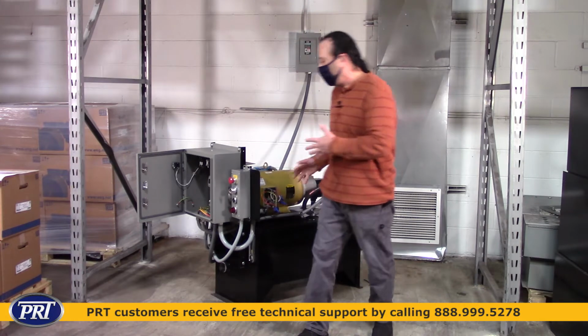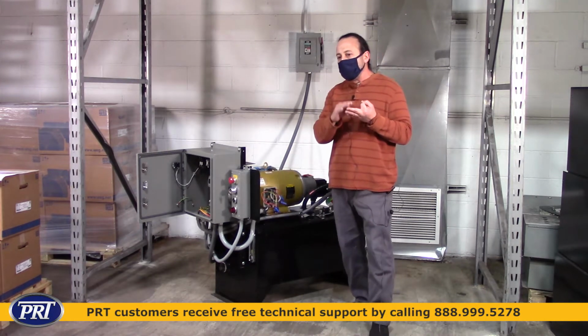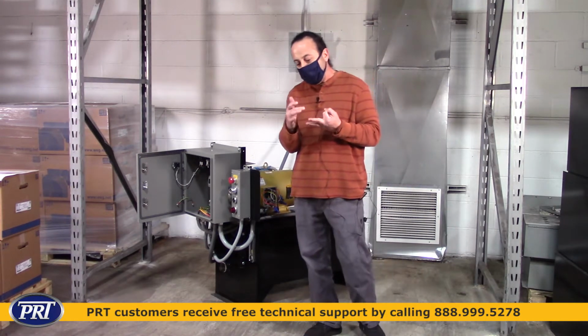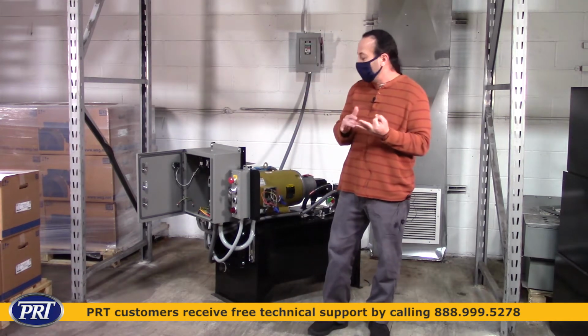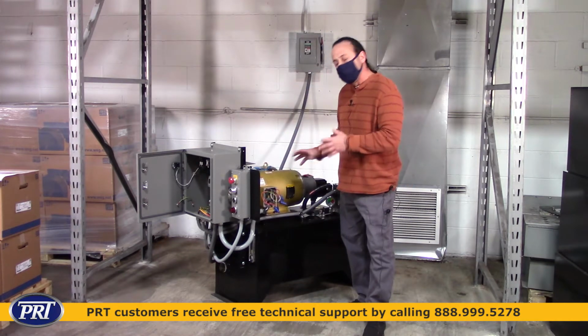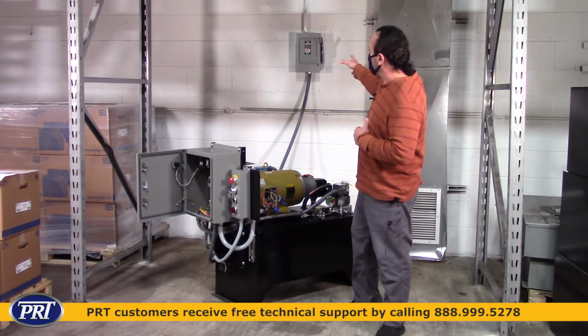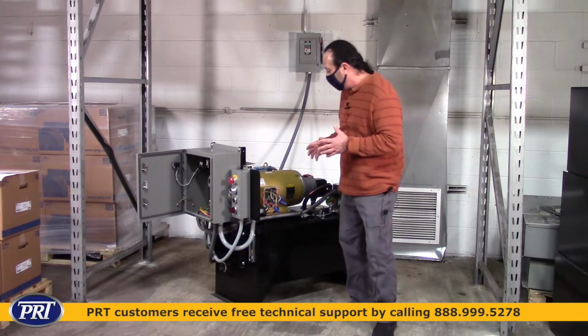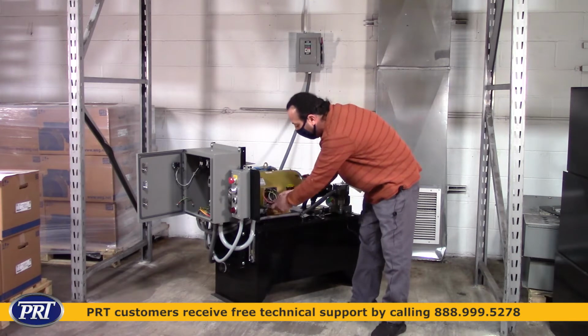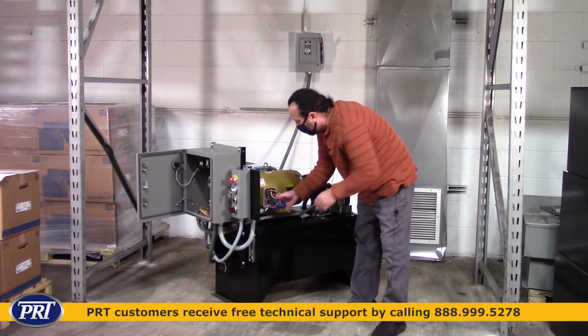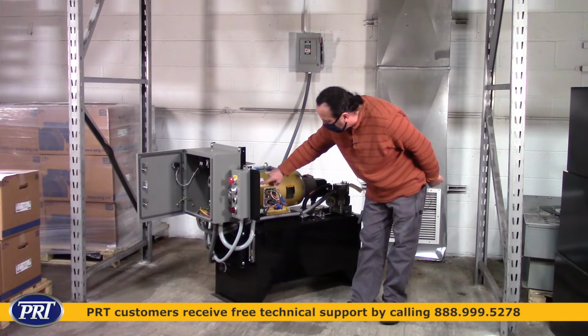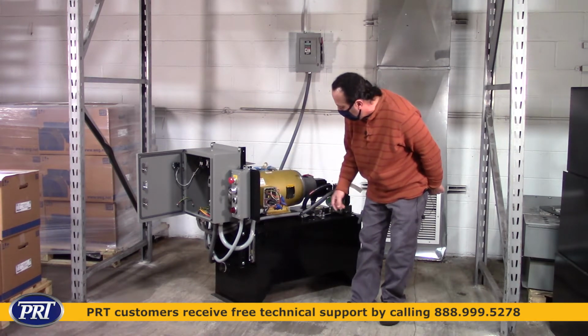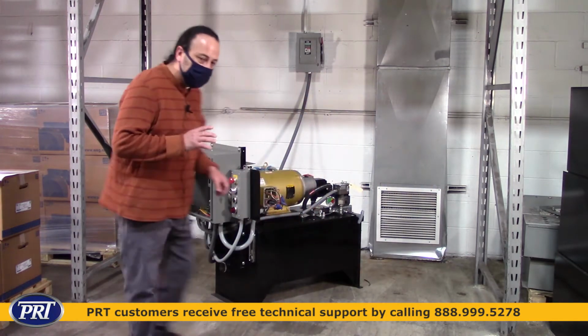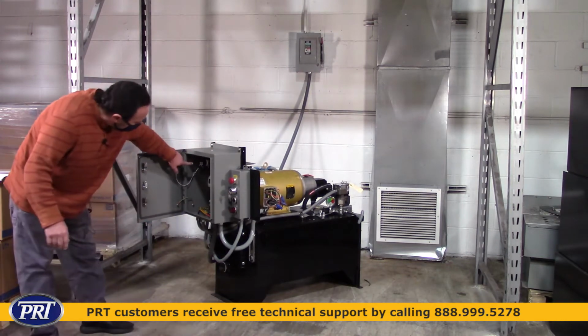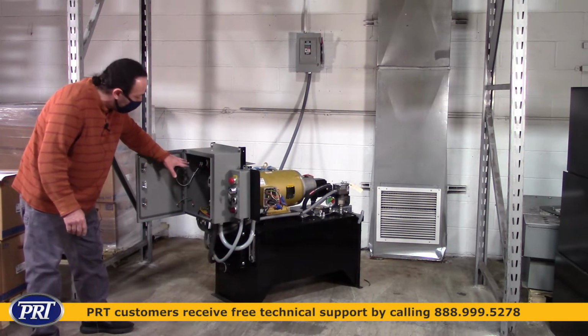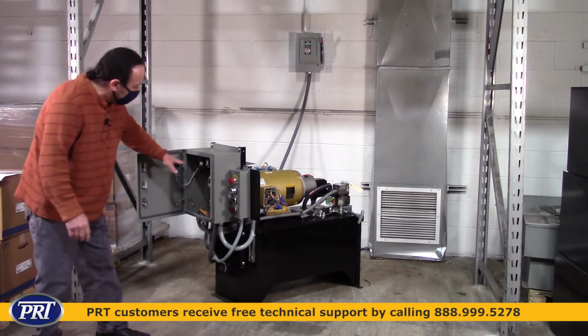Now, these are three-phase units, so you can have three different types of three-phase power, which is 208, 230, 460, and this motor is interchangeable for all of it. This panel here is set up for 230, so the thing that we had to do to this motor was wire the motor head correctly to 230, and there's a sticker right here that tells you low voltage, high voltage. The other thing you've got to do, after you do the motor, is come over to the transformer, and you've got to set the transformer for the high voltage or the low voltage.